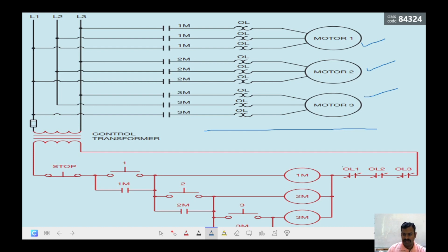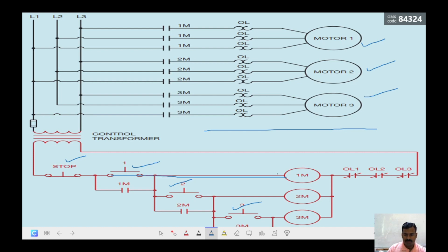In the switching elements I have one stop switch to stop the process and three start switches to start the respective machines. When switch number one is closed, the path for motor one or coil one is closed in the control circuit, so the current reaches coil number one and this relay contactor coil is getting energized. When it is energized, the contacts of this contactor close.